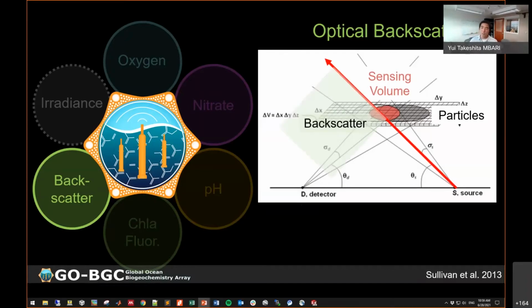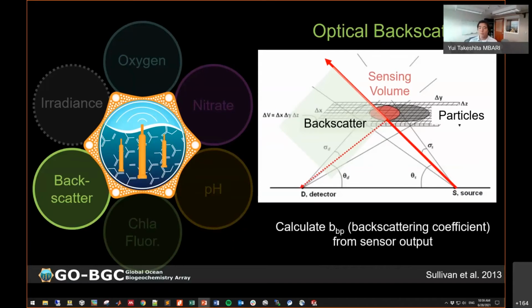Backscatter refers to the part of the light that is scattered between 90 degrees and 180 degrees from the incident light angle. The detector measures a part of this backscatter and integrates it to the whole scattering volume. From that measurement, we can calculate something called BBP, which is a backscattering coefficient. That is a direct sensor output. Then we use relationships that we observed in the ocean to go from backscattering, BBP, to POC, or particulate organic carbon concentrations.